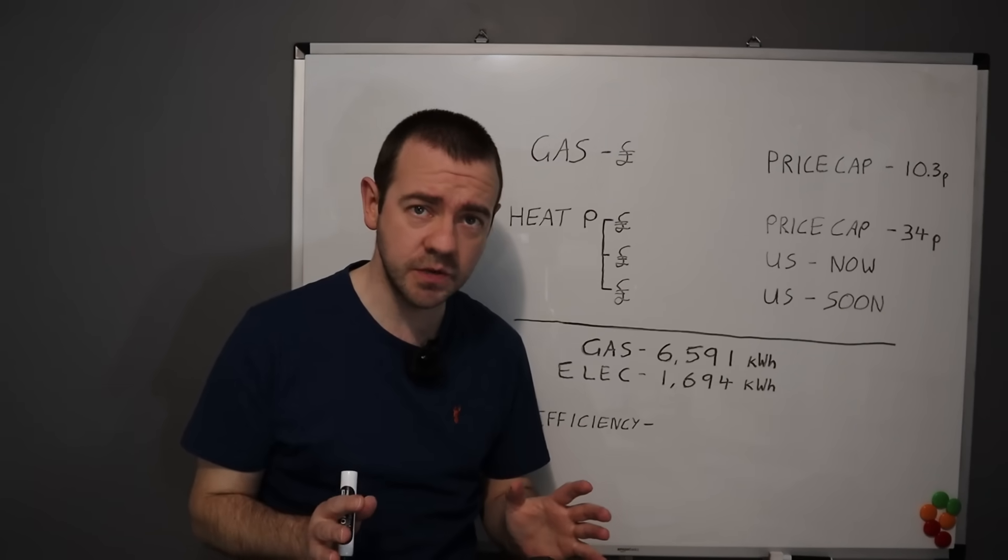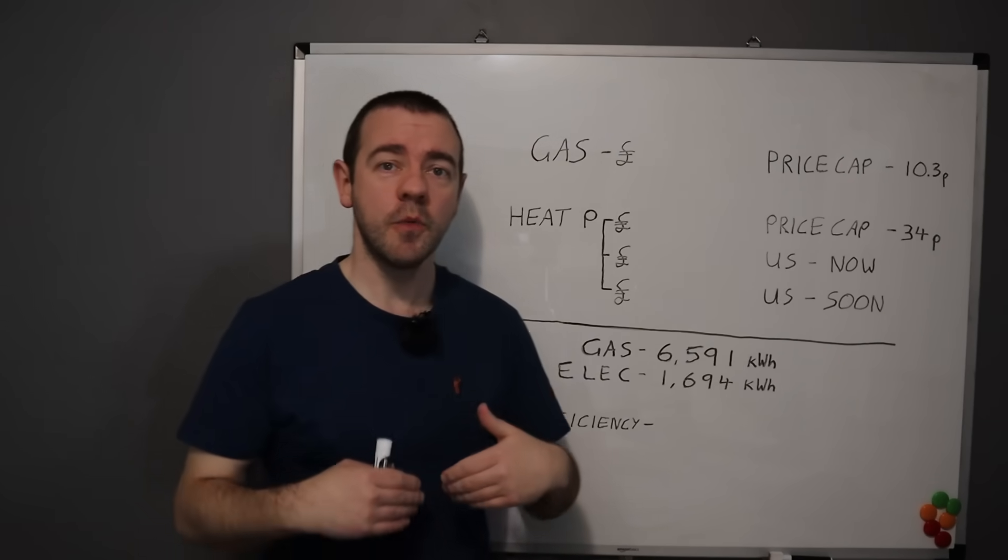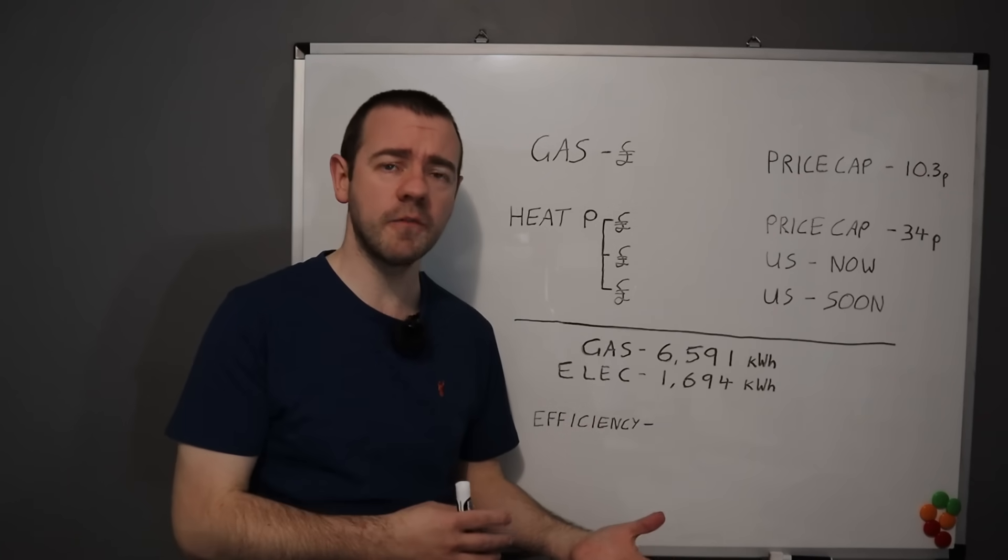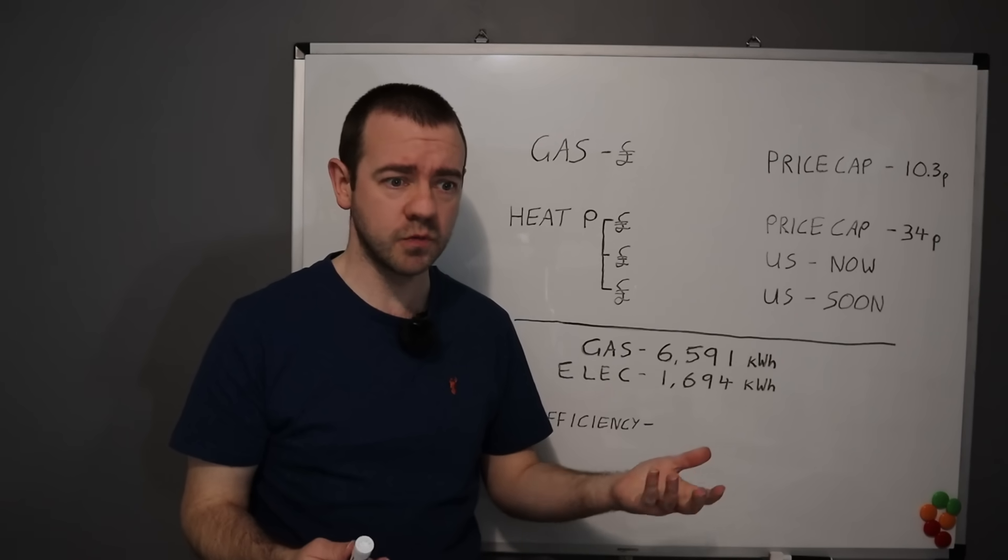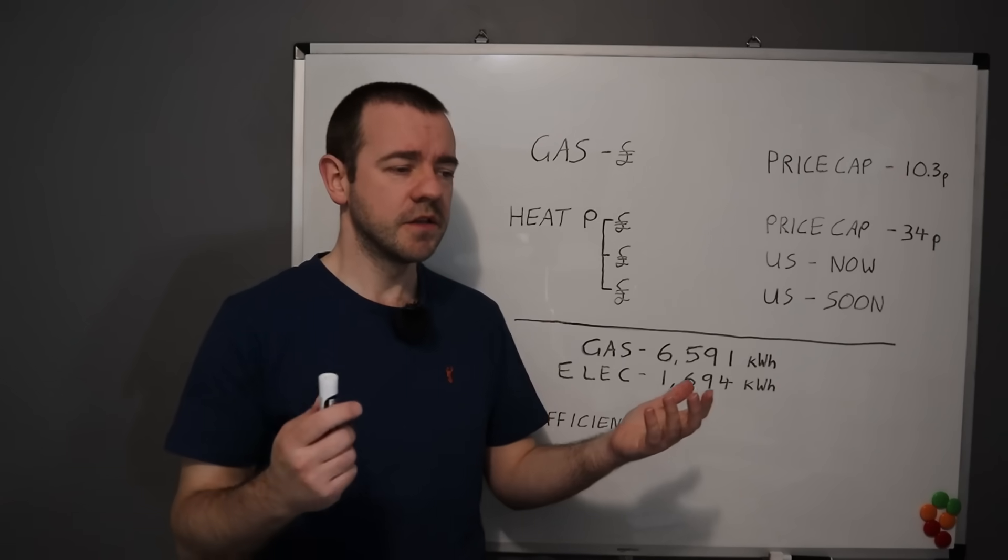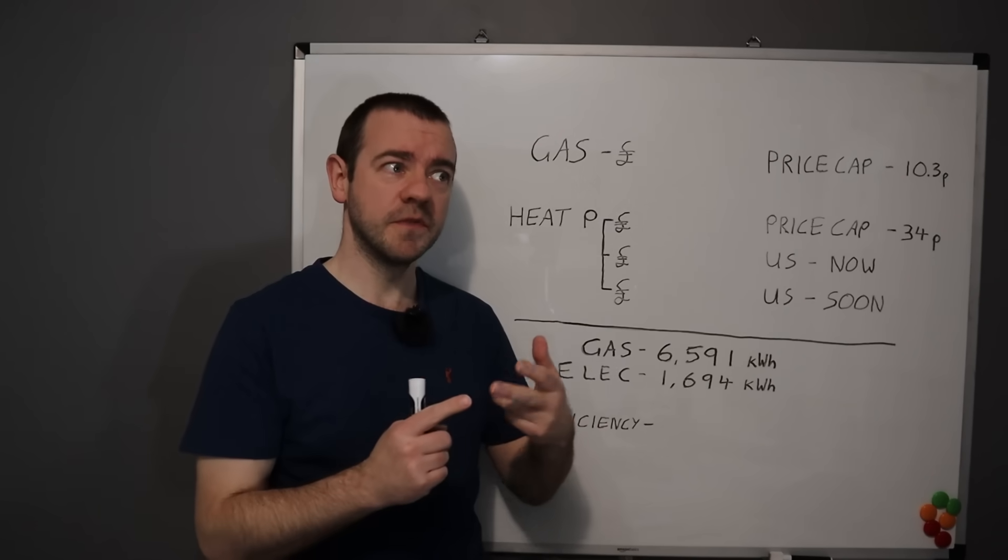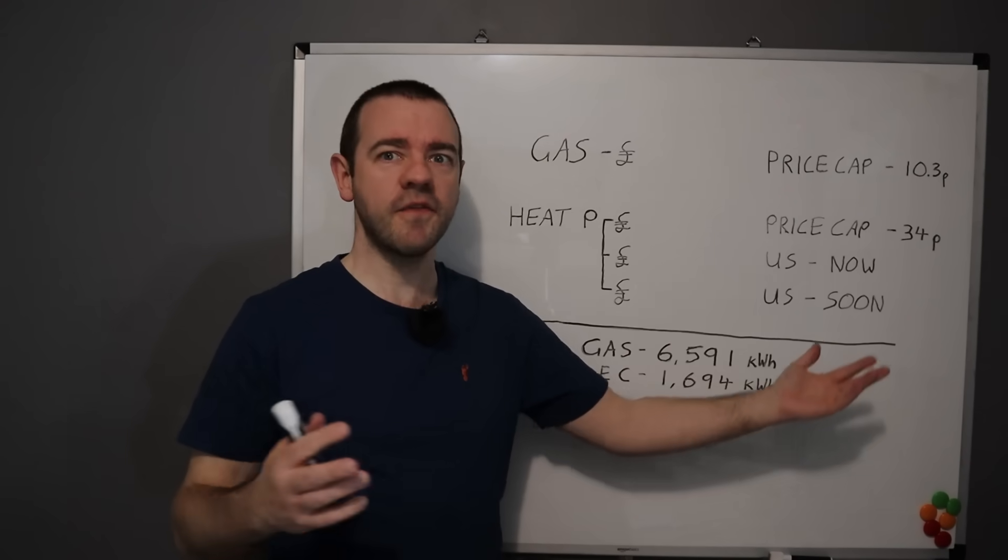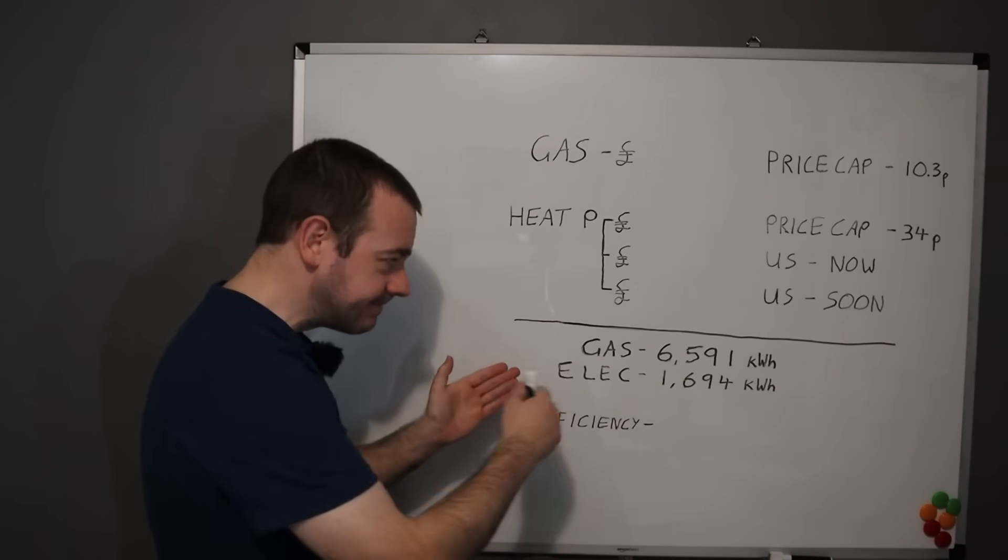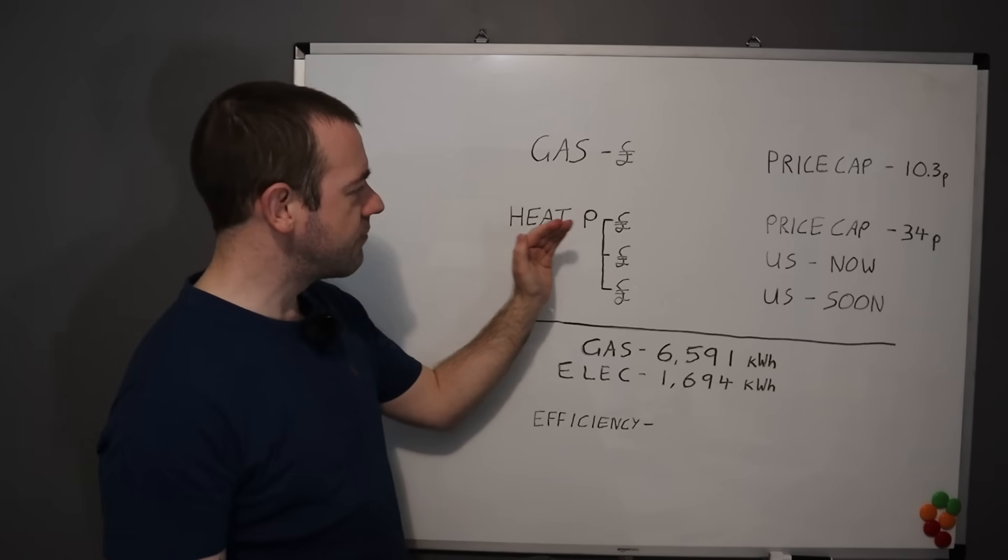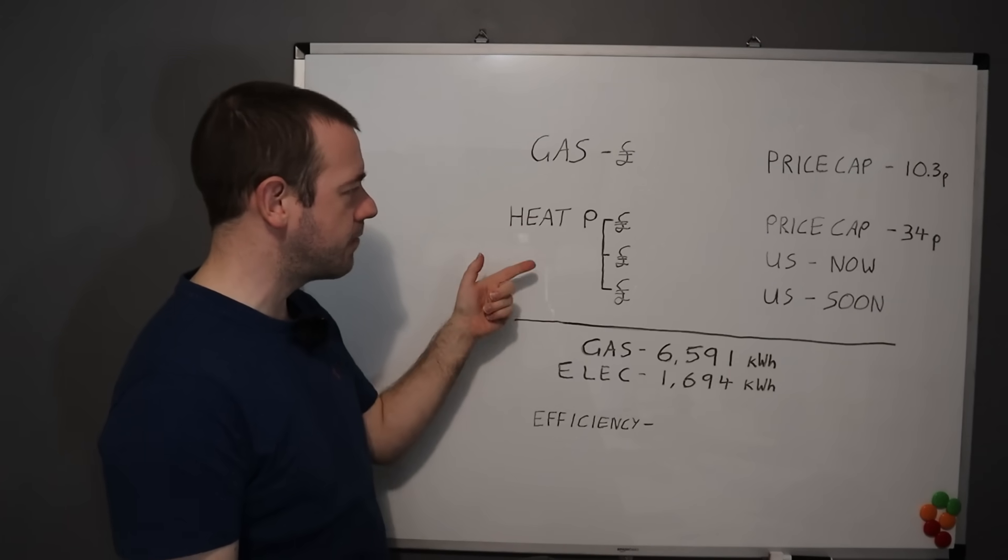And before anybody says this, because again, as I mentioned earlier in the video, we don't have a massive immersion heater outside defrosting the heat pump. It does it itself using the four-way valve reverses the refrigerant route around the heat pump like it would if cooling. The compressor doesn't run. We've also disabled from day one the immersion heater in the hot water cylinder.